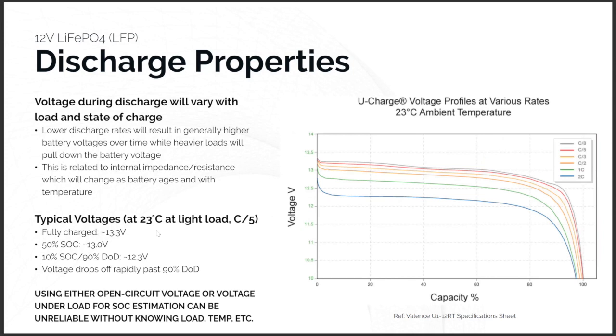So I've got some typical voltages. Say it's a light load, using that 40 amp hours divided by 5, so I'm drawing 8 amps. Fully charged, you're at about 13.3. At 50% state of charge, you're at about 13 volts. And when you're essentially fully discharged, you're down near 12 volts. From the chart, once you get past that 90% rate, it's a cliff. So my big takeaway here is that just doing a voltage measurement on your battery may not tell you where you're at.